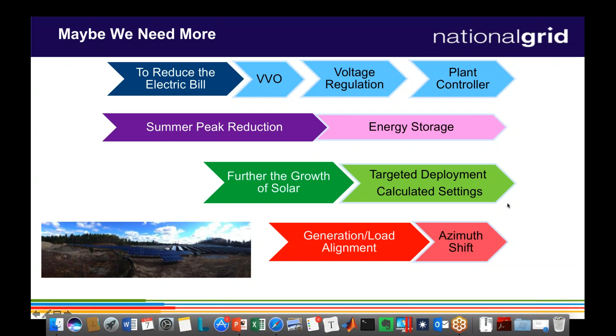Now, National Grid has several phases of solar—I'll pick up with our Phase 2 program. You may guess our first program was Phase 1, and the third was Phase 3, duly named by an engineer. In Phase 2, we looked to leverage advanced inverters, and I'm glad to say we've deployed those and are working on picking the best settings—understanding, across the 16 megawatts or 18 sites we've deployed, how and what functions to use to benefit the feeder.